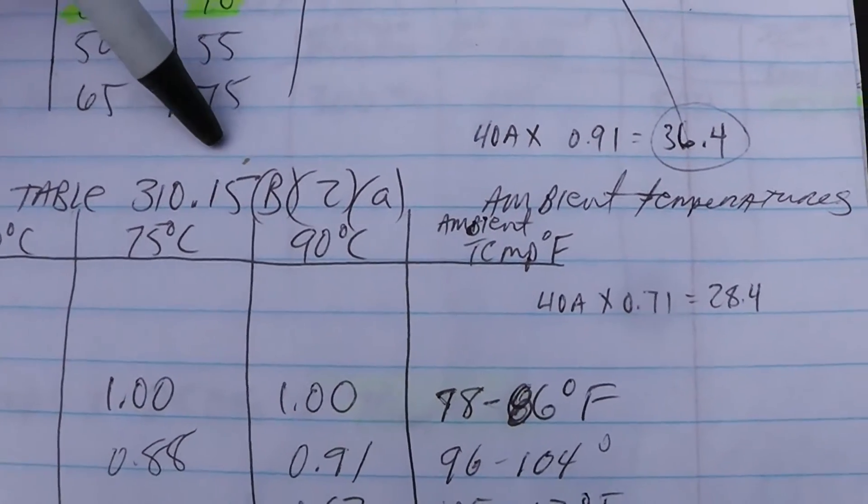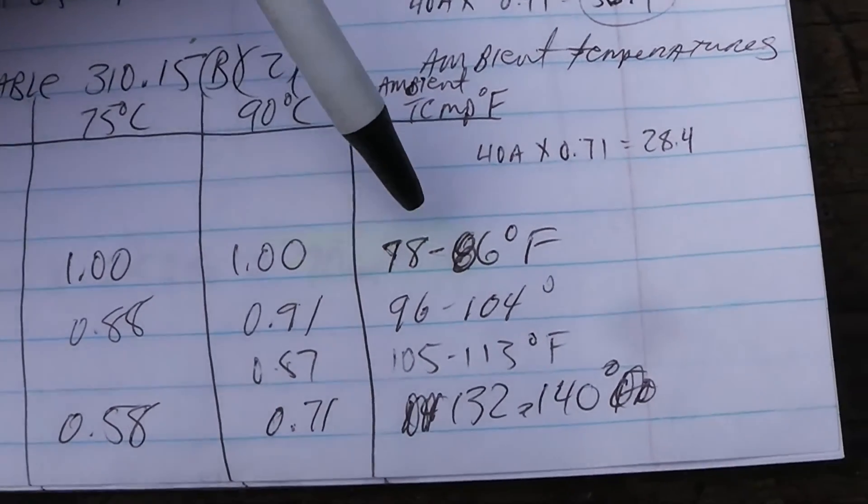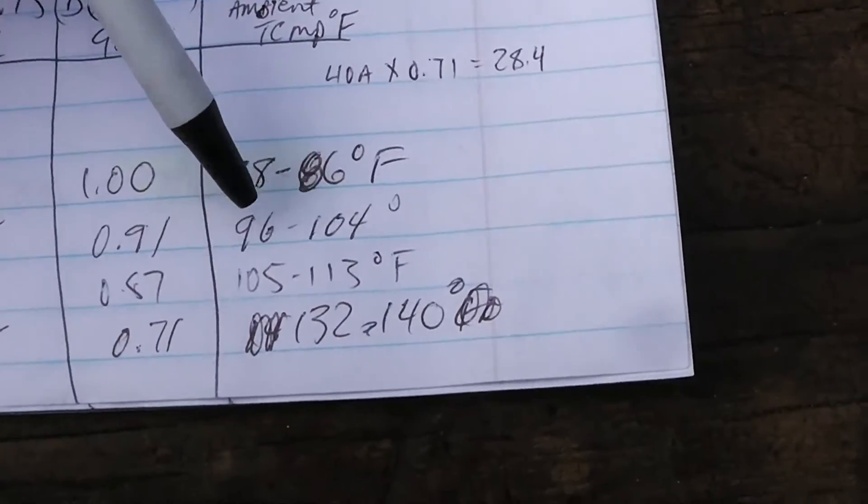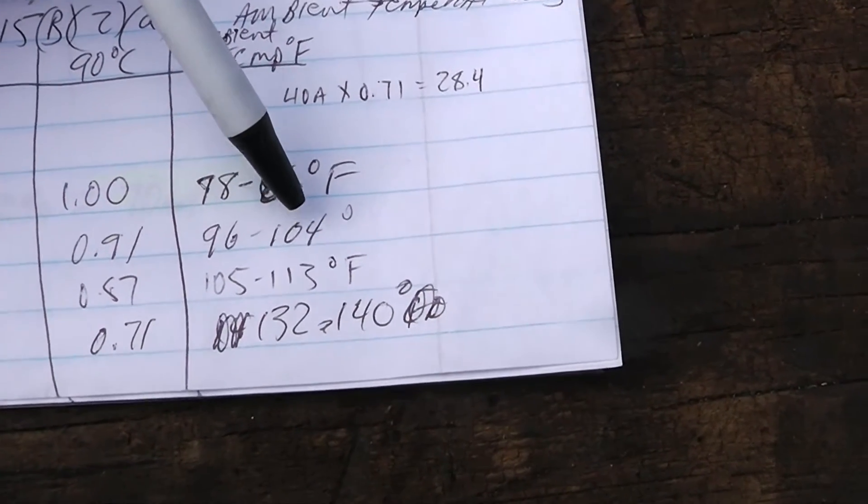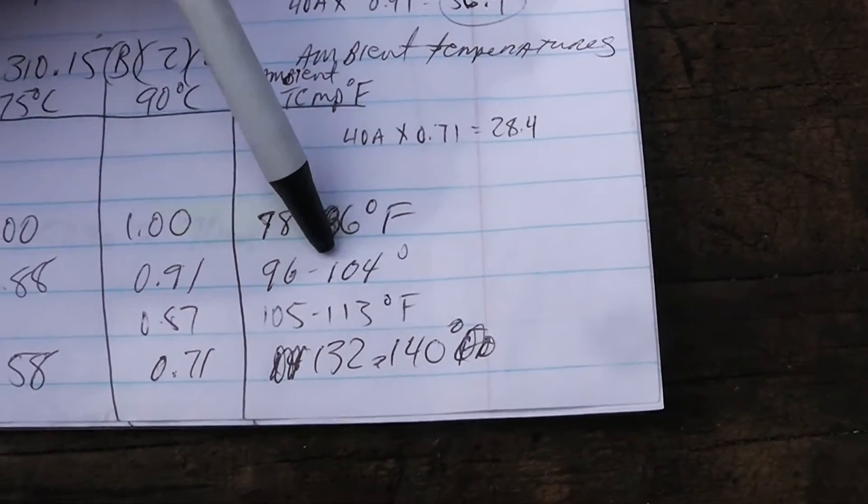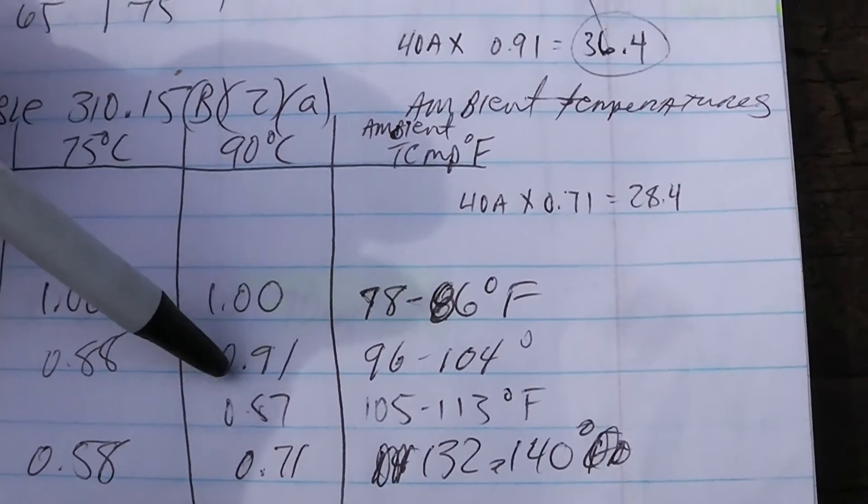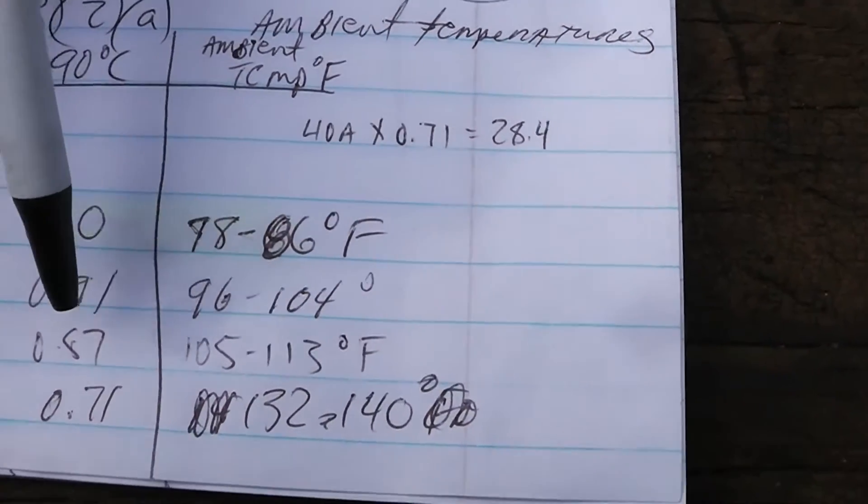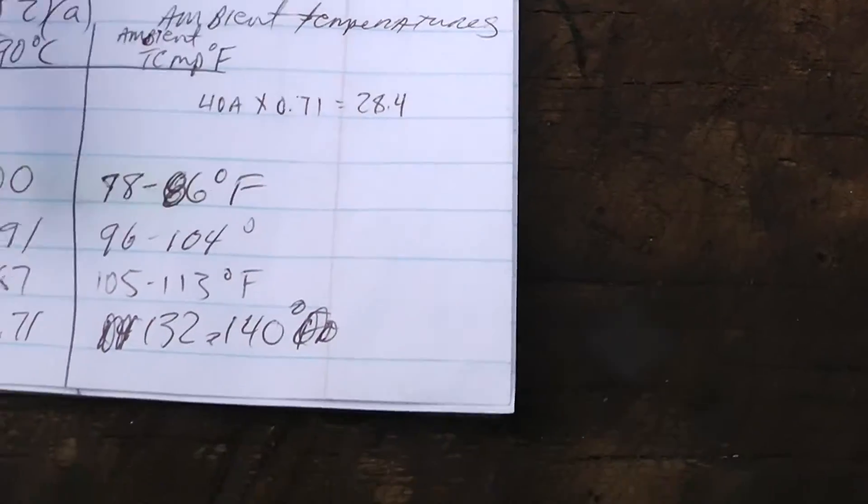You have to derate the conductor according to the ambient temperature. If you go to table 310.15b2a, you'll see a table of ambient temperatures. We're in the 90 degree column, and if our temperature around here is this, we don't derate the wire. Let's say our ambient temperature is 96 to 104. I'm in Florida and the highest temperature we've ever had here was 99 degrees in 1985, so I'm in this range. If we multiply - we're in the 90 degree column - 0.91 times the 40 amps, that says that wire can handle 36.4 amps.